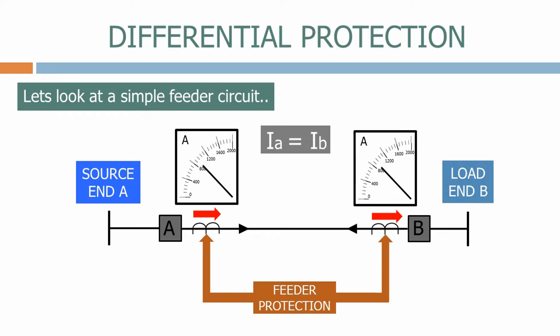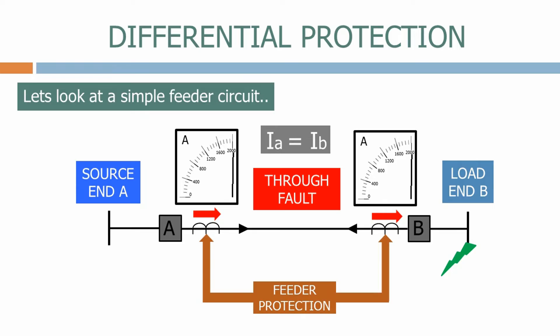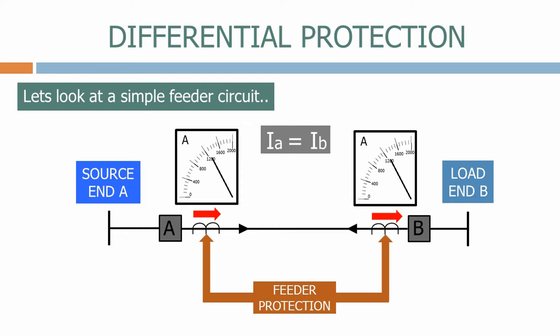Let's now apply an electrical fault at End B and see what happens. The current magnitude will now increase substantially at both ends A and B, but they will still have the same magnitude and therefore the feeder protection system will not operate. This is called a through fault, as the fault current passes through the protection system. Let's now remove the fault — the current on both ends returns to normal.